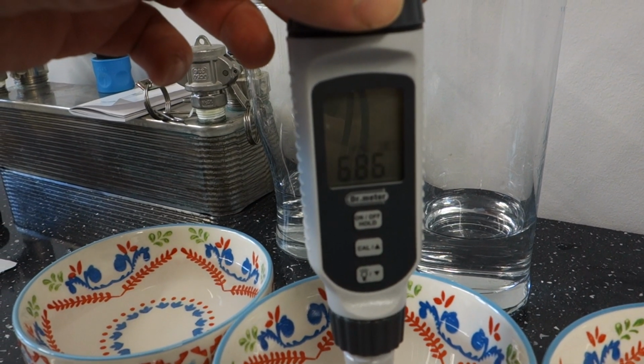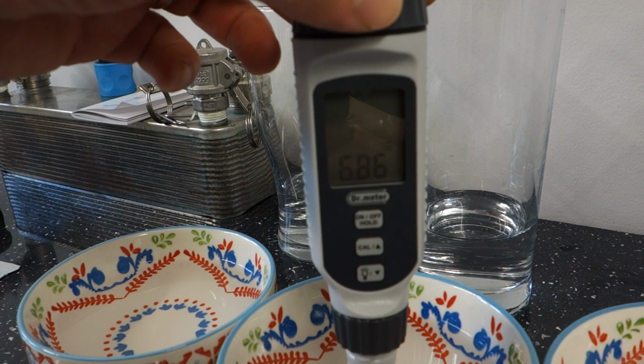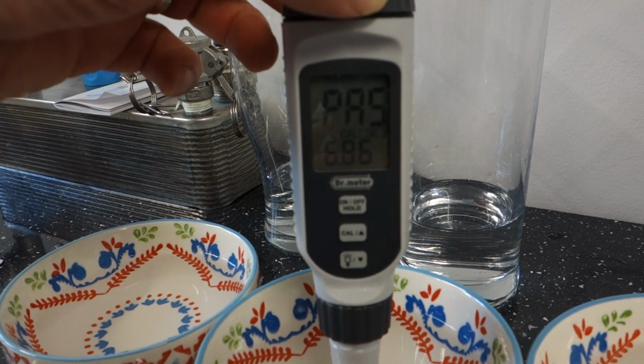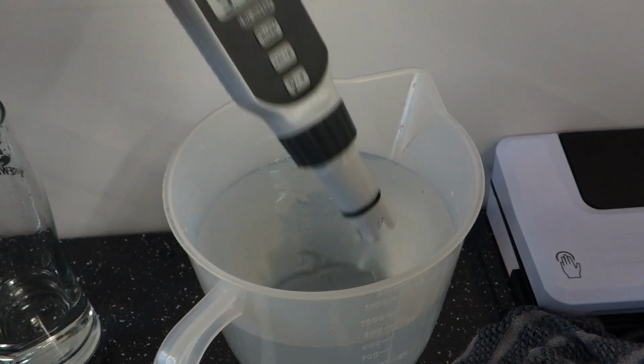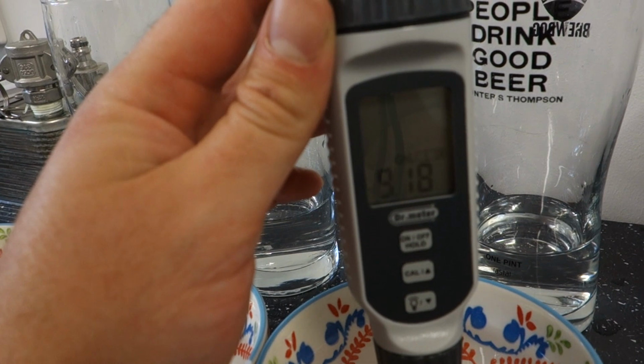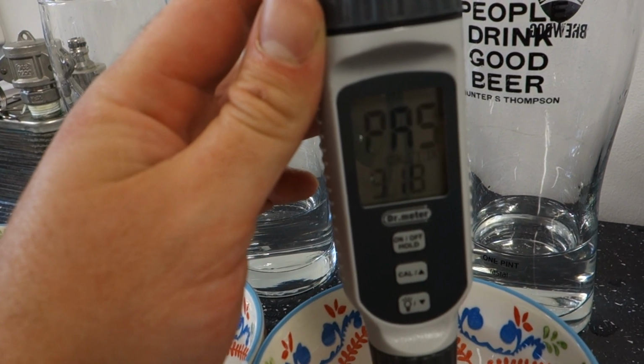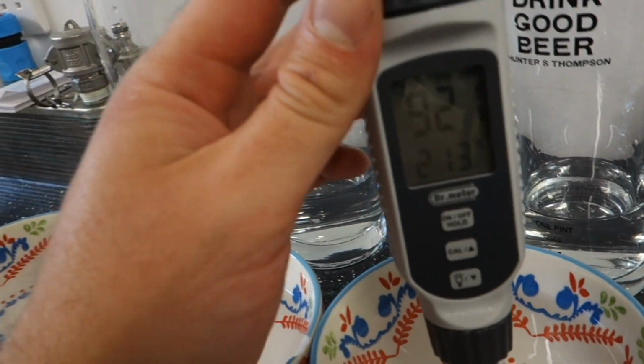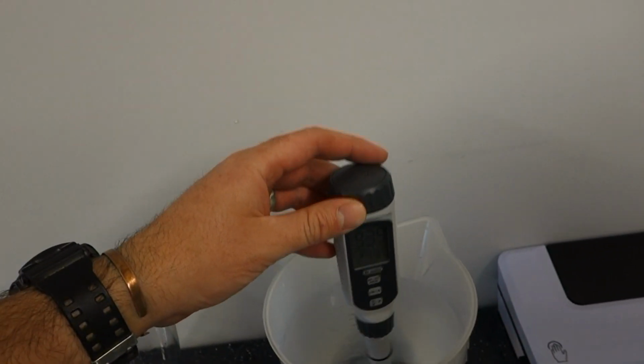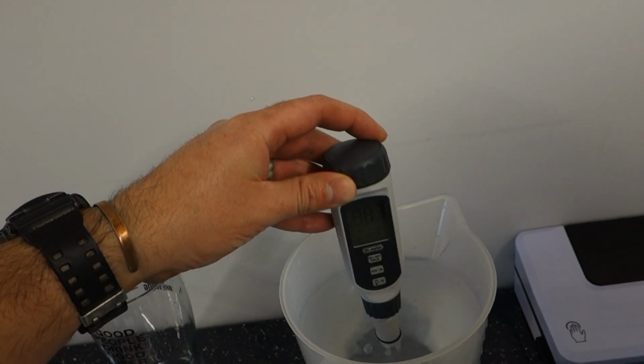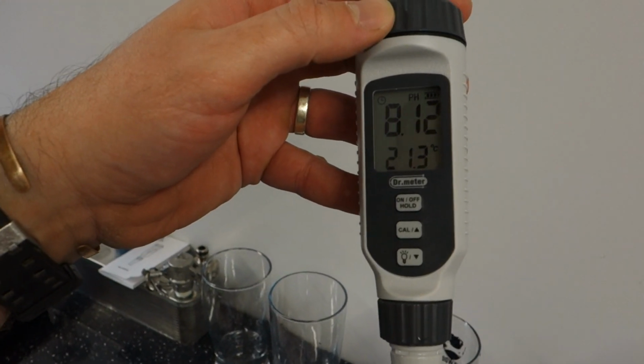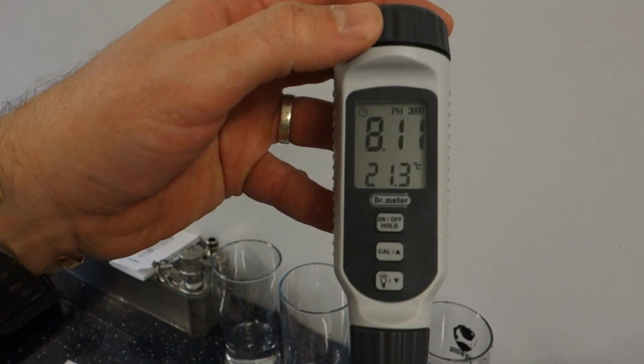Now it's moved on to the second buffer, and it's running through the second calibration. There we go, pass. So again, rinse her off, and it's now saying to move on to the 9.18, which is this one. Passed. So that's it now, the calibration is done. I'll give her a rinse off, like so, and you can see now that it's back to the reading mode, where it's giving temperature and the pH at the top. So it's all rinsed off.